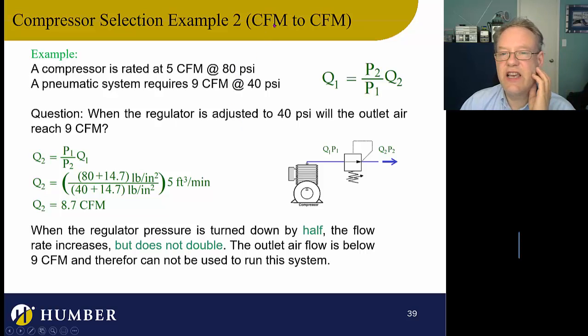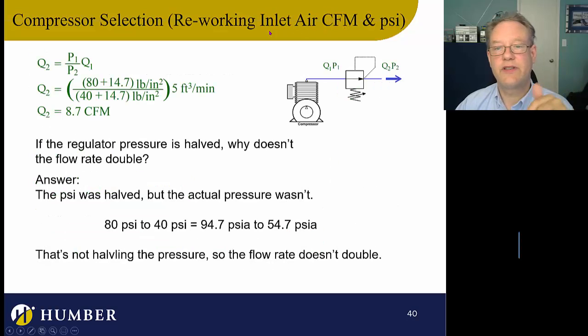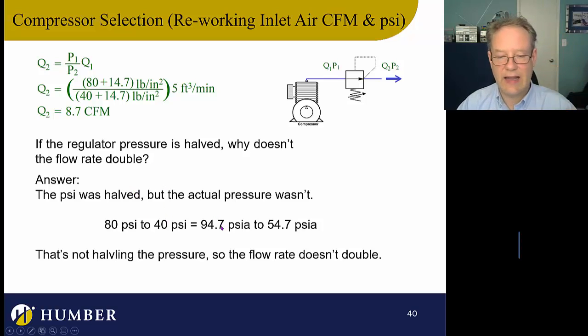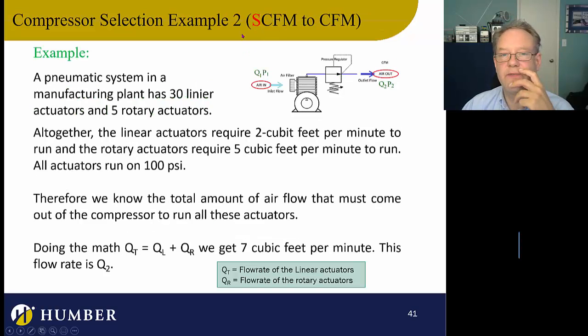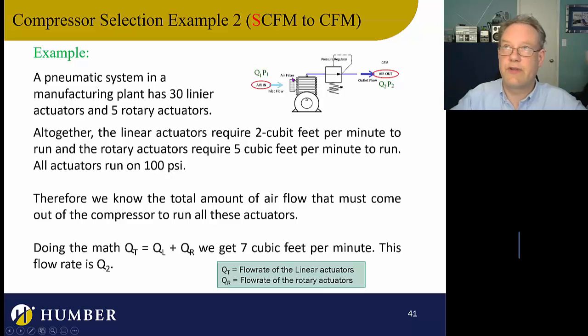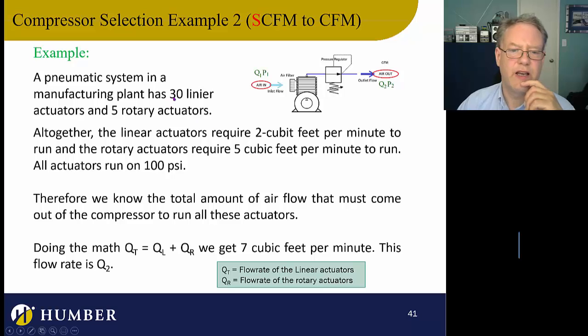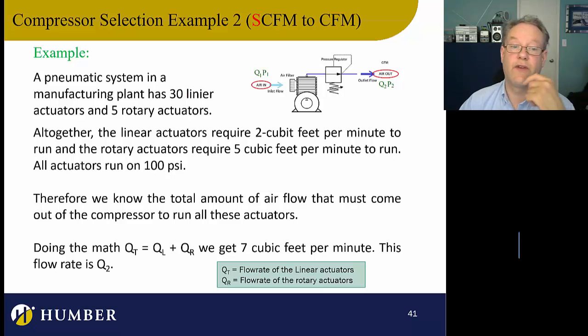Now let's look at SCFM to CFM. We have a compressor rated for SCFM — it just gives you the SCFM without specifying inlet pressure, because it's understood to be atmospheric. A pneumatic system in a manufacturing plant has 30 linear actuators and 5 rotary actuators. The linear actuators require 2 cubic feet per minute and the rotary actuators require 5 CFM. They're all running on 100 PSI.